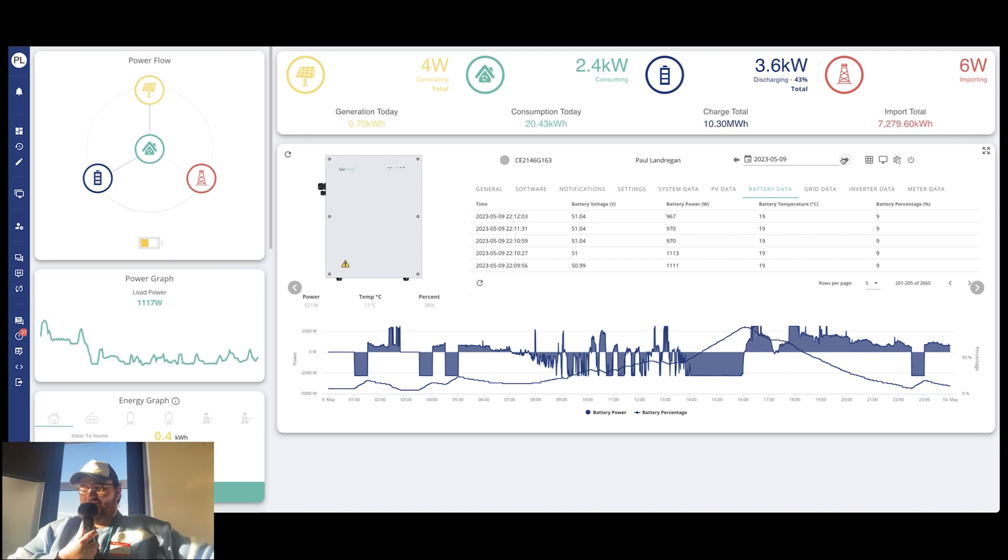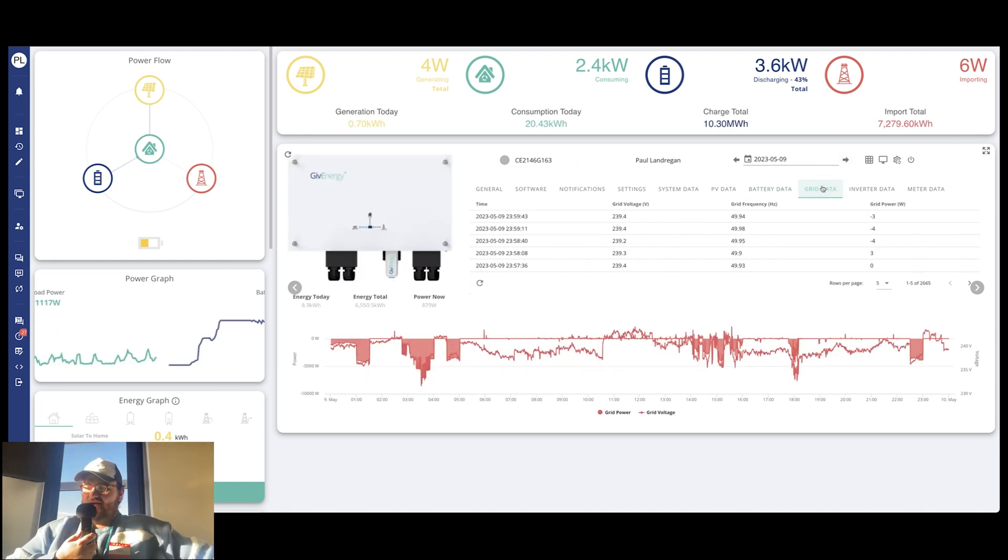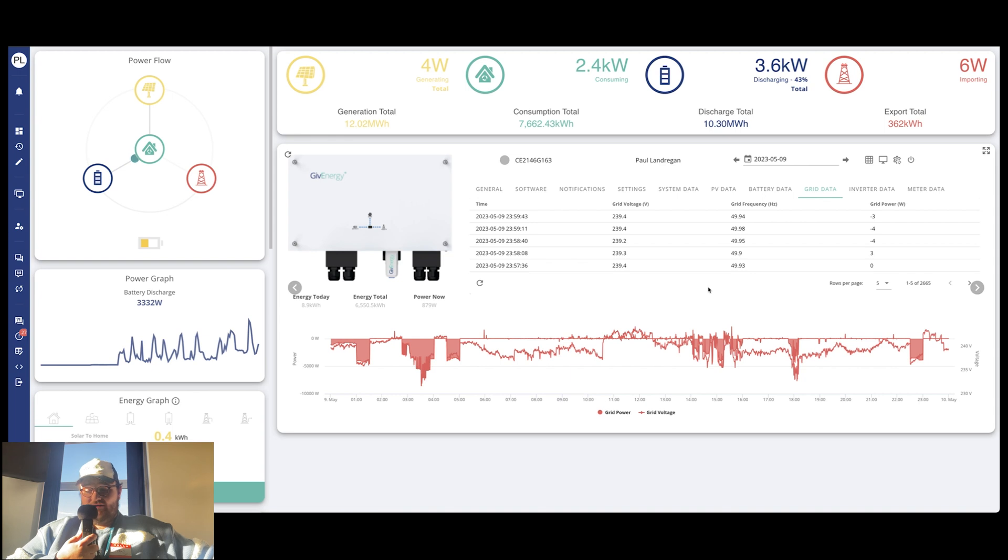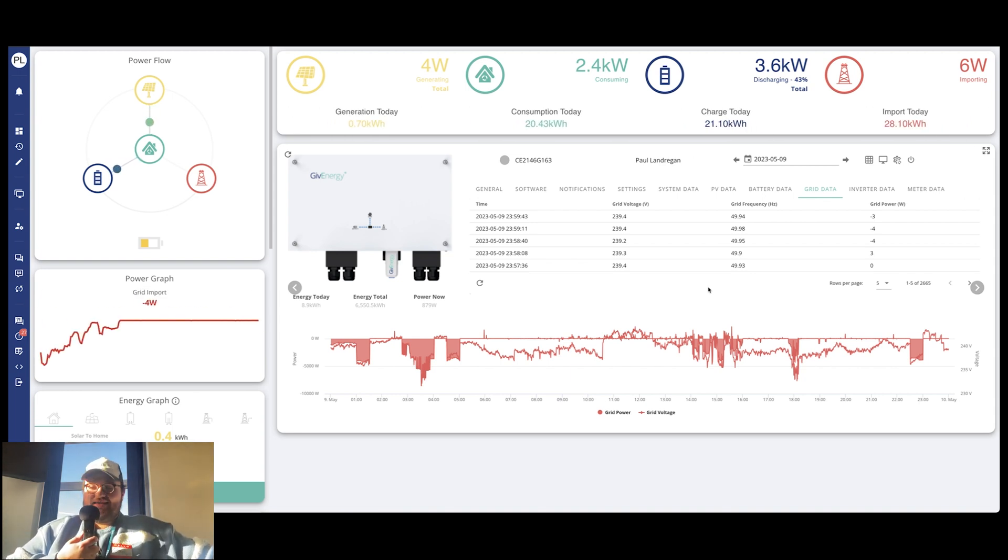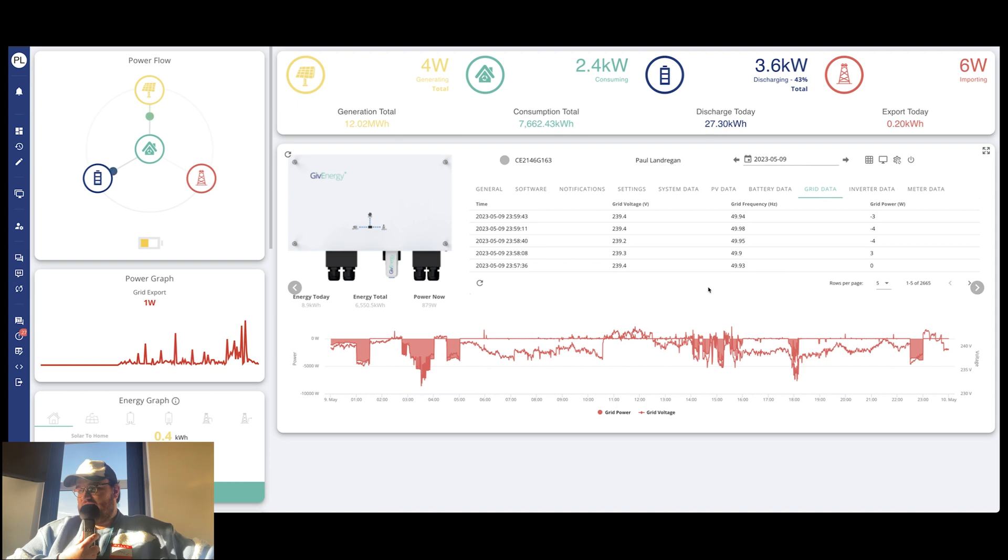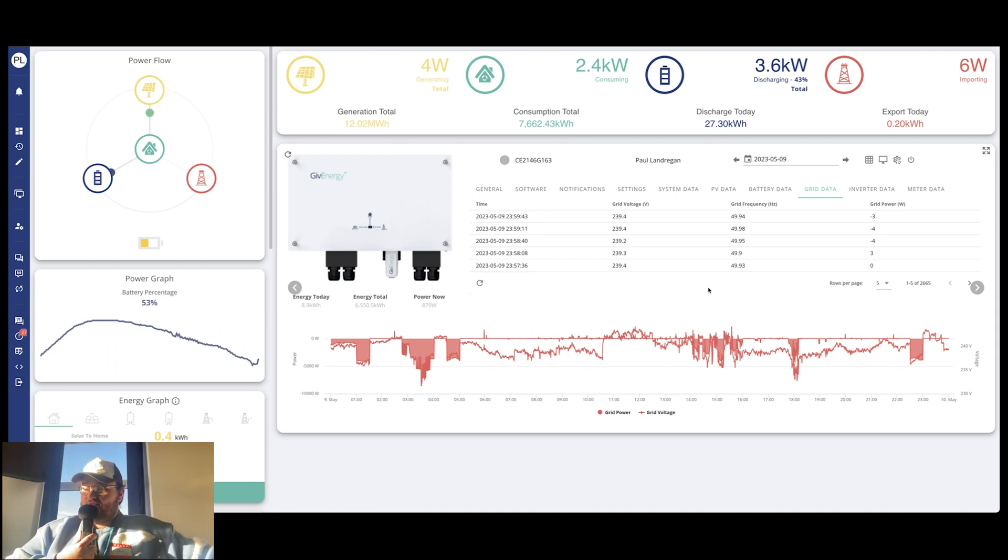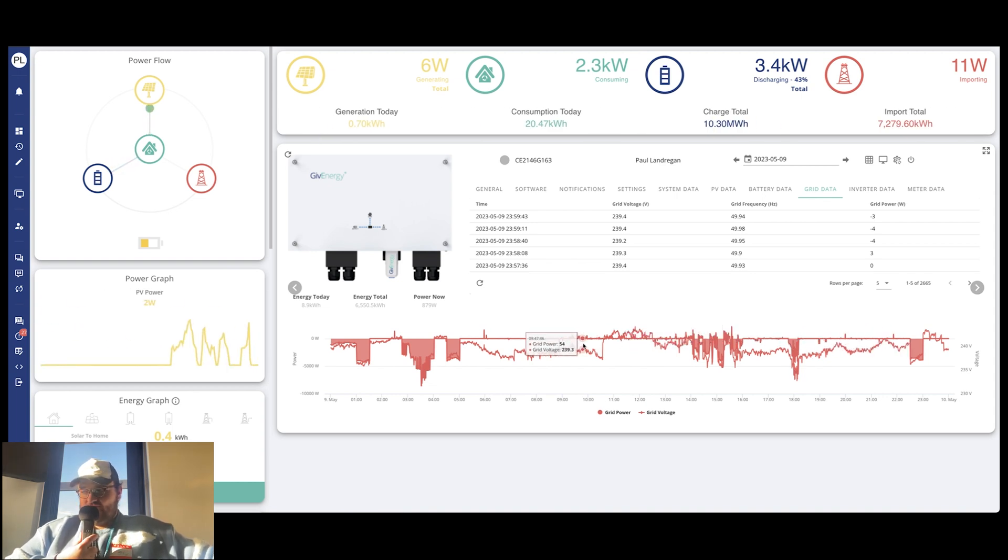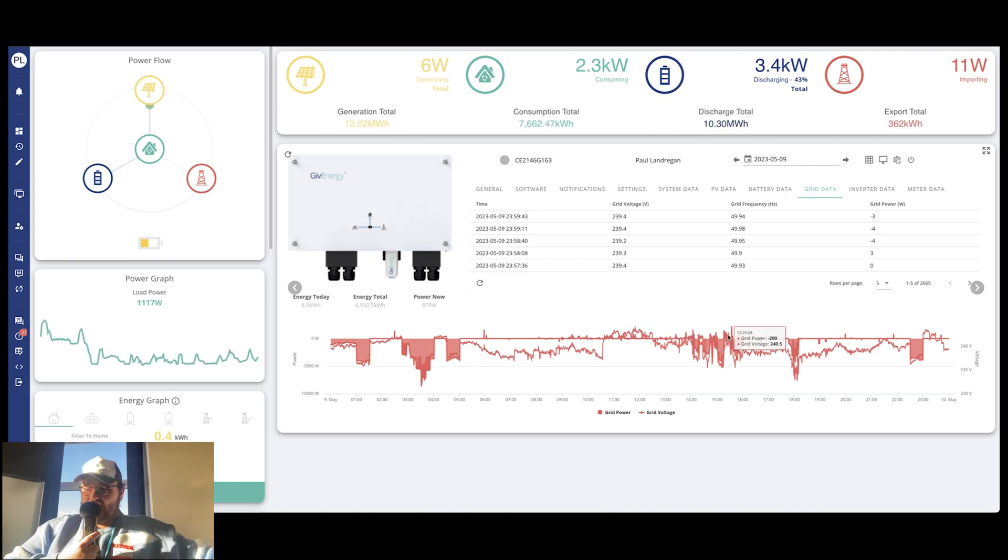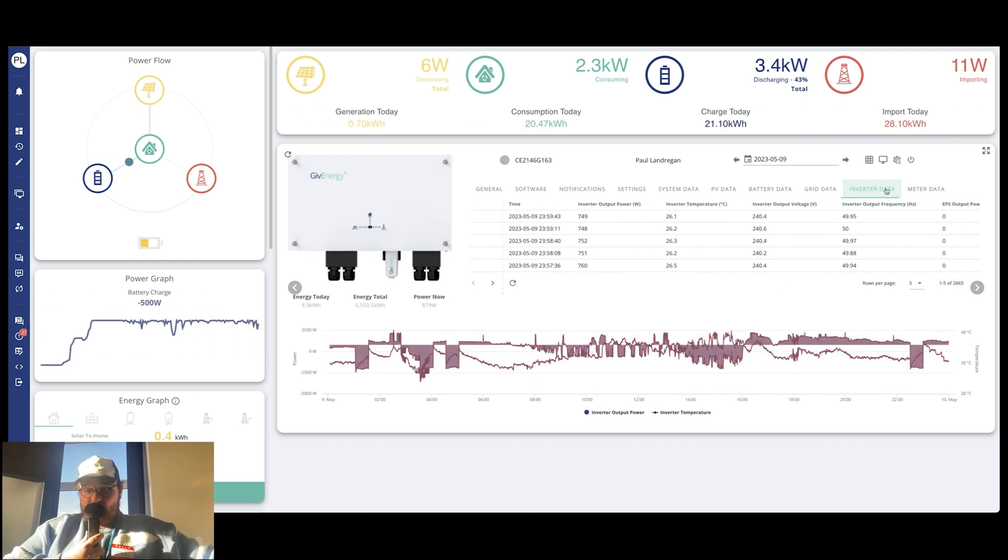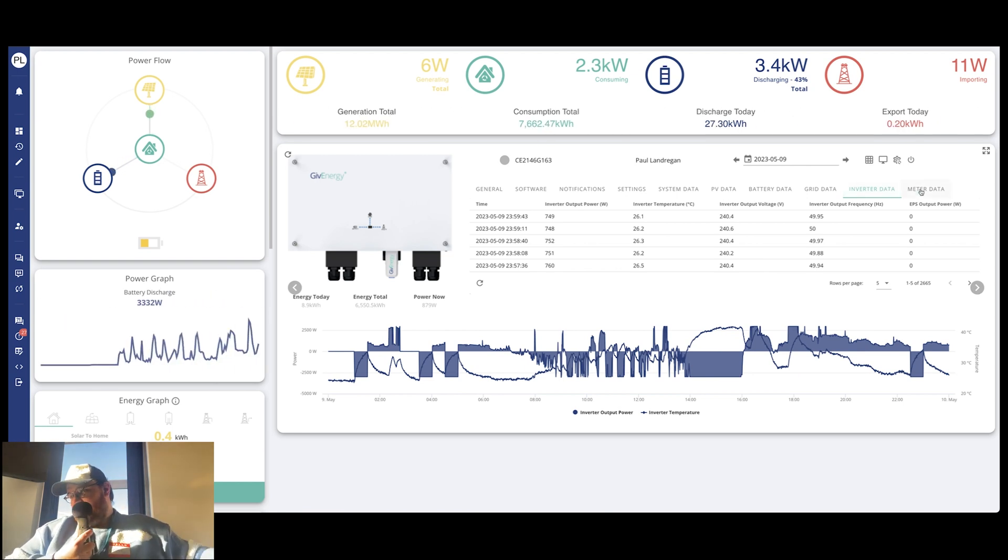Next up, we've got the grid data tab. So again, just like everything else, this relays how much you're either sending to or taking from the grid. You can see grid voltages and frequency and all that kind of stuff as well. This is really handy. Typically, if you ever get a grid voltage warning, if the voltage goes above 253 volts, then you'll automatically get a notification from us saying, hang on, that's a bit high, something's a bit up here and you might need to get in touch with a local DNO or local authority, something like that. Just to check out everything. Again, that's only if it's not working. If it's working fine, don't worry about it too much.